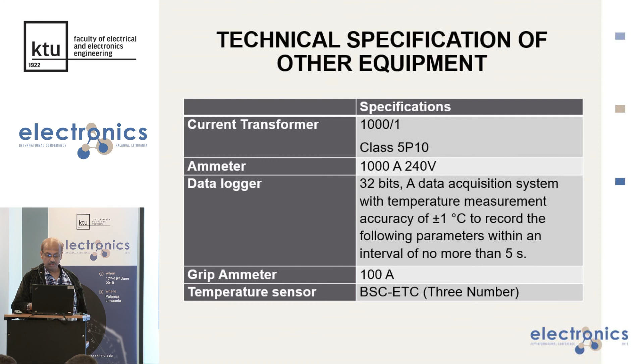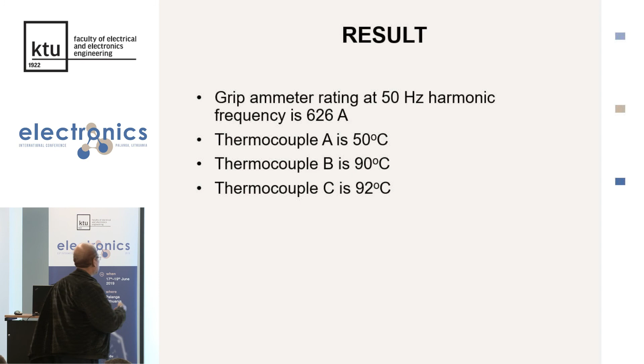And for the temperature rise, thermocouple A detected 50 degrees centigrade, thermocouple B 90 degrees centigrade, and thermocouple C basically 92 degrees centigrade. You know that India is a tropical country. There the ambient temperature is so high that in Delhi two days before, whenever I was collecting my diesel, the temperature was 46 degrees centigrade that day. And Dhanbad is a supercritical zone. There are the mines, and Dhanbad is the coal capital of India. It is declared so by the Indian government. So here thermocouple A is basically the ambient temperature sensor. So the ambient temperature on that day was 50 degrees centigrade.